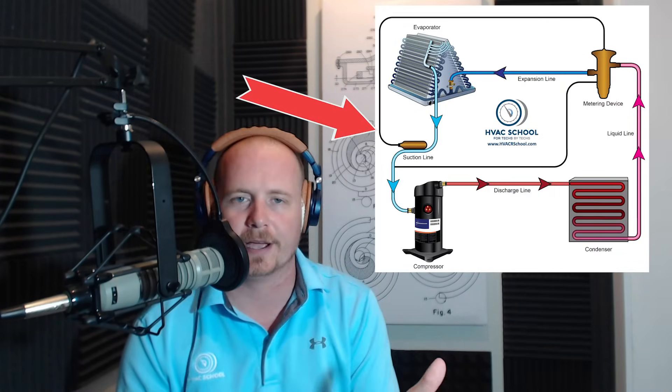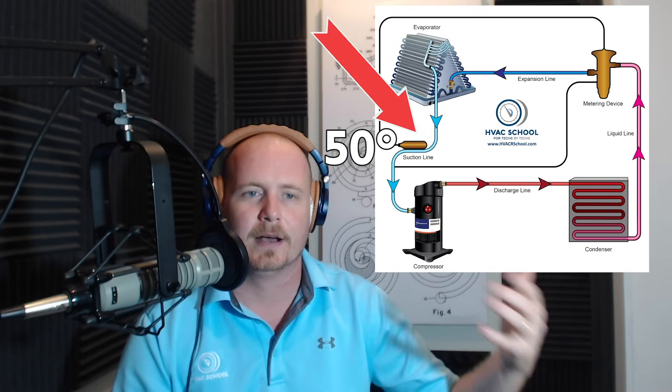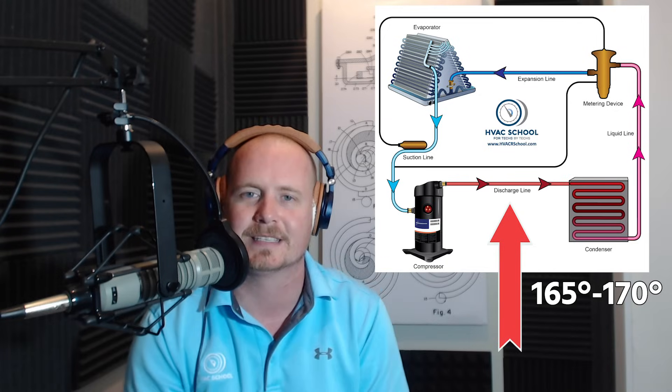The compressor takes vapor from the suction line, pumps it, and sends it out through the discharge line into the condenser. The suction line coming into the compressor is low temperature and the discharge line leaving is high temperature — there's a big difference. On typical air conditioning equipment under normal conditions, you might see around 50°F on the suction line entering the compressor, and then coming out of the discharge line something like 165–170°F.